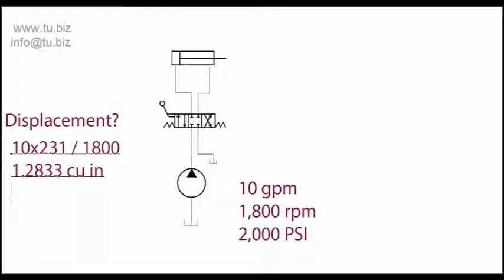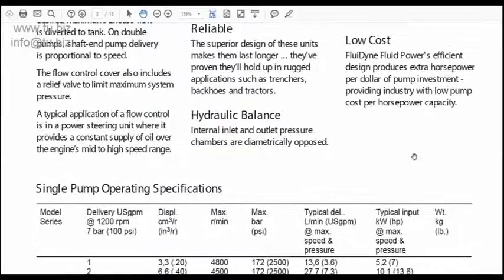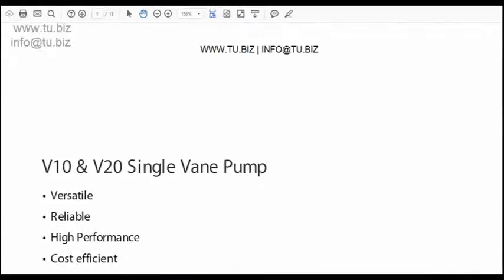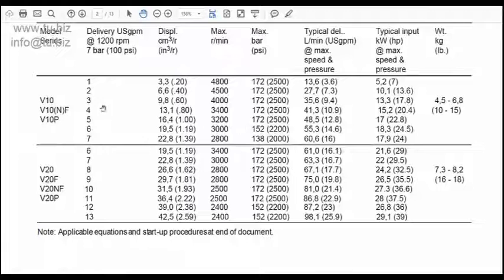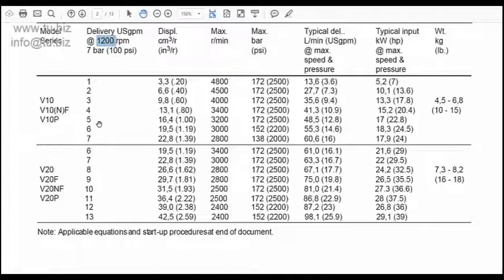We're going to select the pump using this catalog — a data sheet on vane pumps, fixed displacement. On the vane style pump, you can see these numbers right away. It gives you the pump size in GPM, but based on 1200 RPM. So you have to be careful not to say 'I need a 10 GPM pump' when you're not running 1200 RPM — you're running 1800 RPM.